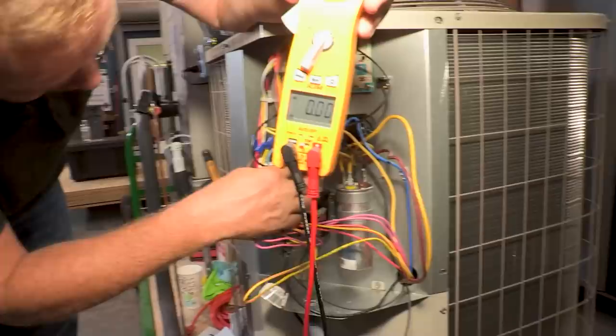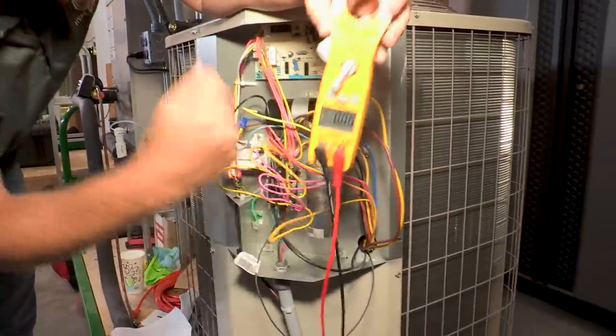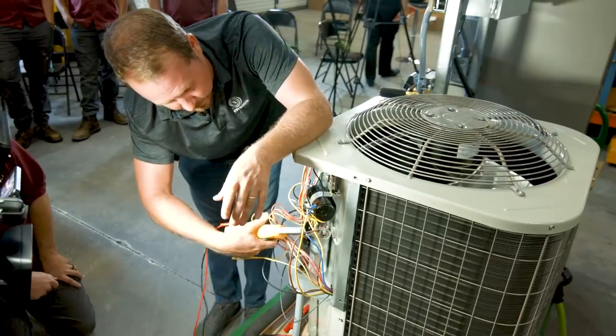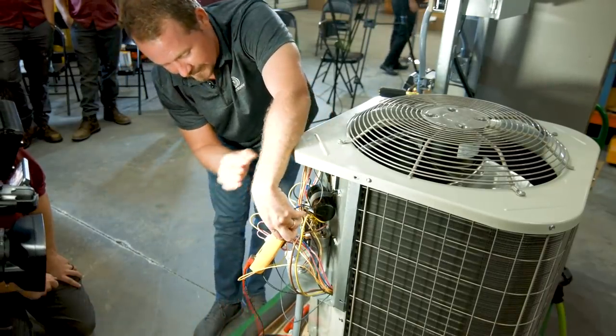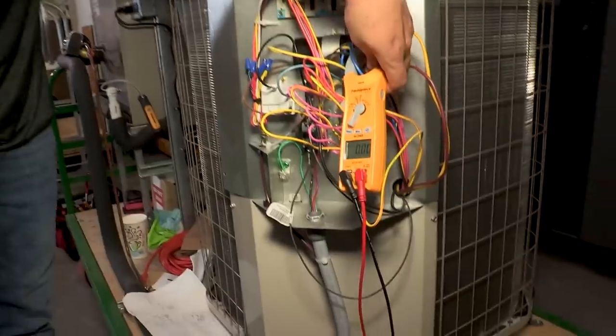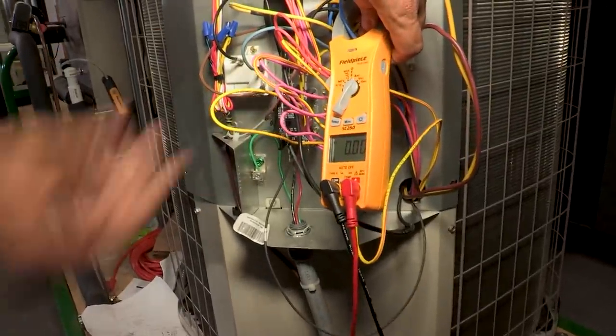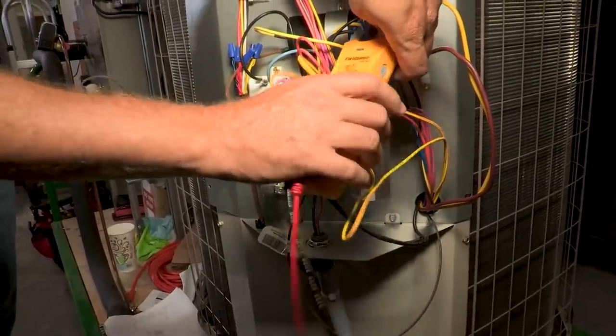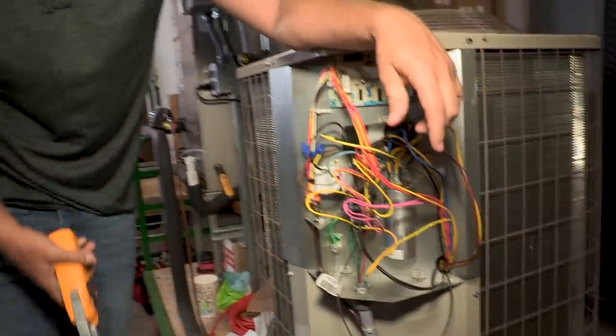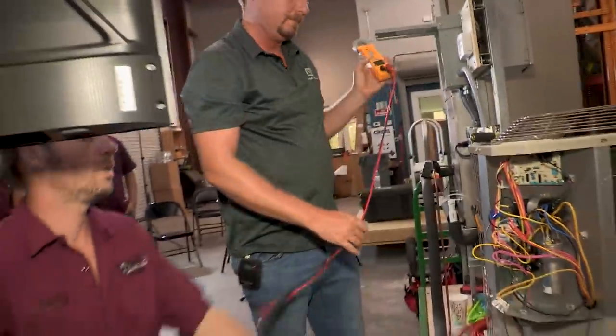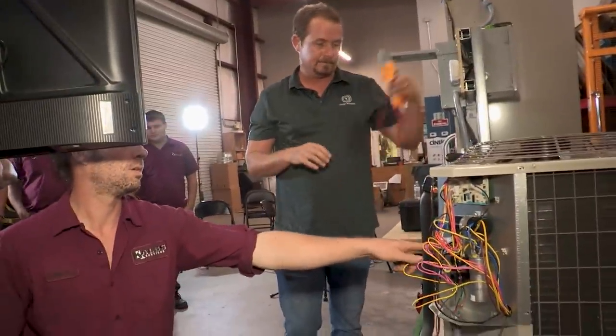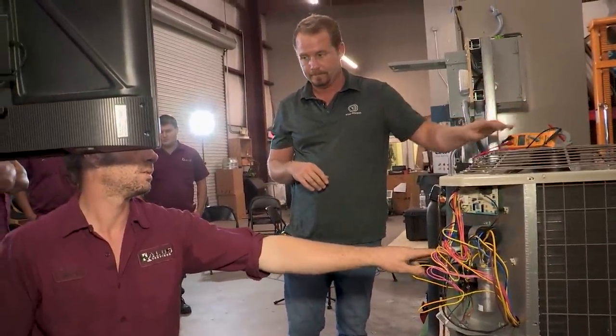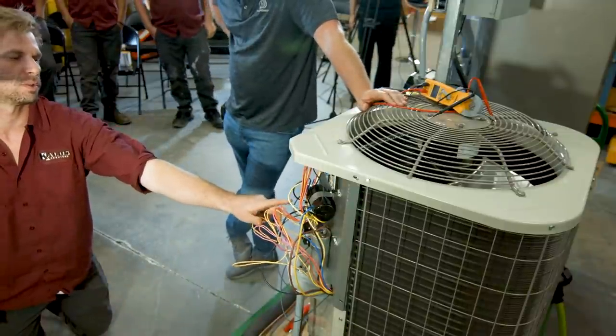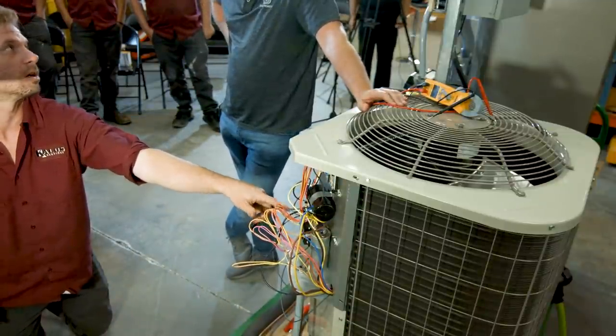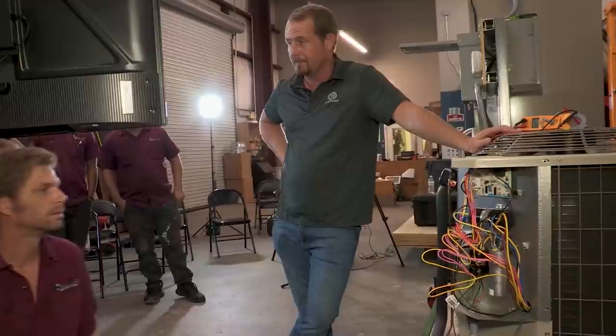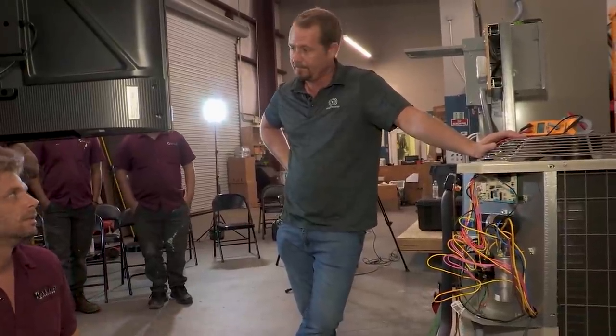So in this case, our start winding is this one right here. If we measured our current on our start winding itself with the hard start kit in, it would draw higher inrush current on our start winding. And with our start capacitor out, it would draw lower. Now again, you'd have to put it on the inrush setting on your meter in order for that to function. Or if you're just wondering if it works at all, you could measure it here and it would tell you if your capacitor is empty or the relays. True. Yep, you could just do it there. Good point. That would be another good way of doing it.